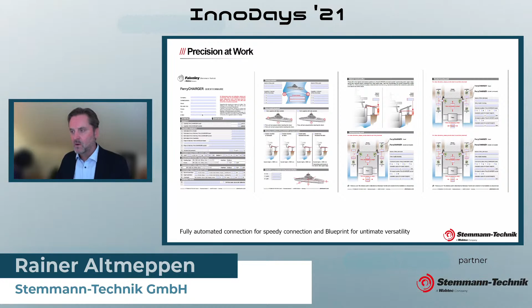Here we have a pontoon, which compensates the tide. If you cannot use a pontoon because the ferry charger stands on land, then we have this vertical tower, which compensates up to 5 meters, or the bow ferry charger, which can compensate up to 8.50 meters of vertical tide, as we have it on the North Sea or the Pacific Ocean. In the Mediterranean it's not that much, but the unit is flexible enough to also charge ships with different berths.